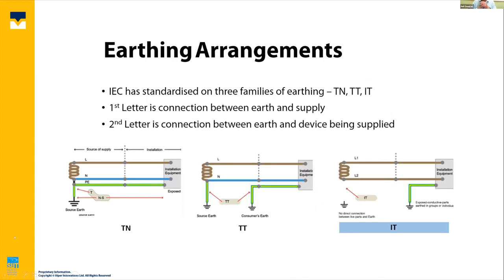Now, what do I mean by an IT system? It comes from a definition which the IEC have set up, and they utilize effectively two letters to define the earthing system of any network. And what you can see is that the first letter defines a connection between the supply and earth. Is there a connection or not? And is it connected to the neutral? The second letter is talking about the connection between the earth and the consumer, so at the far end.